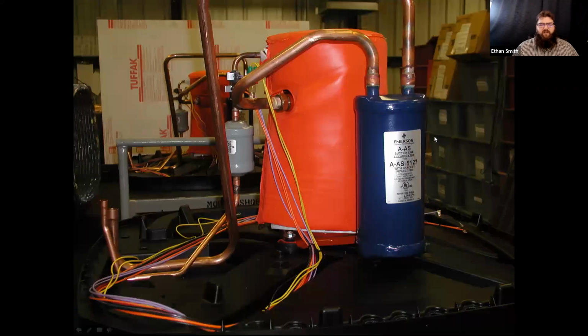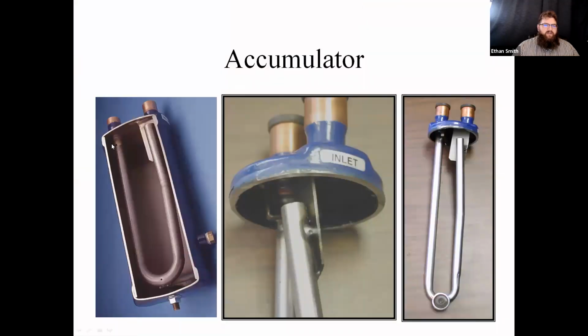So the inside of an accumulator is very simple. It's basically just a giant can. If we cut that can open, the port that goes into the compressor is on the left here in this picture. That port is designed so that it picks up gas off the top of the can. It does go down to the bottom of the can. It's got a little oil pickup down at the bottom, and it's usually got a screen on it. We've knocked the screen off of this one, so you can see the little hole that's there. That will pick up any oil that accumulates in the bottom of the can, and then it draws that back up to the compressor.